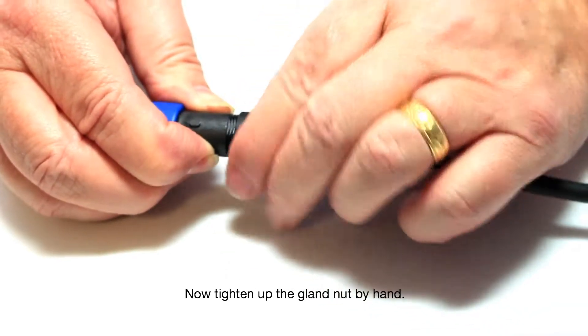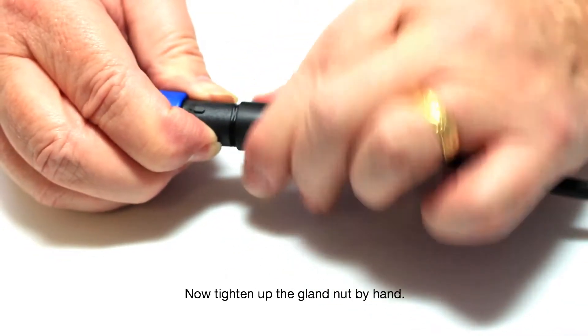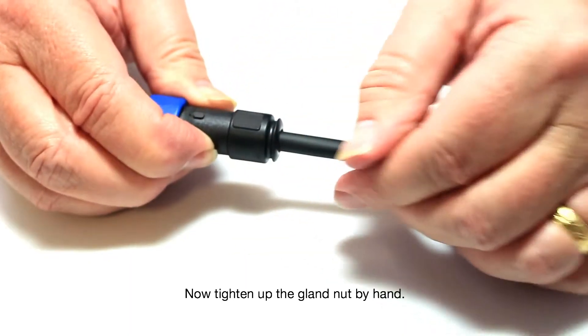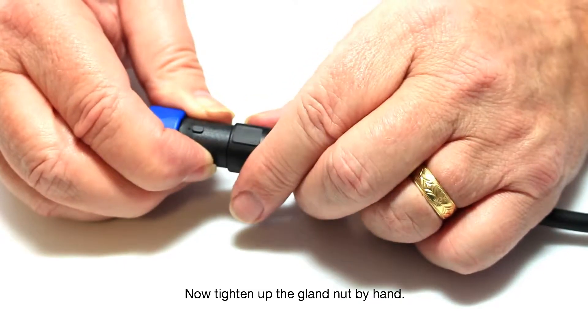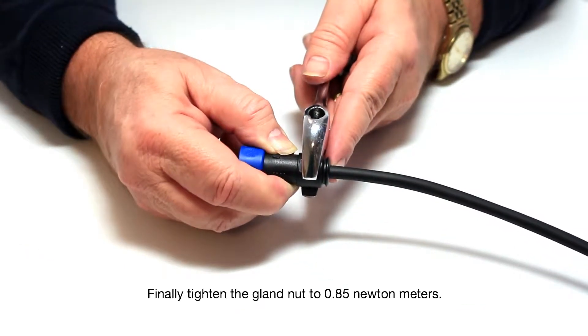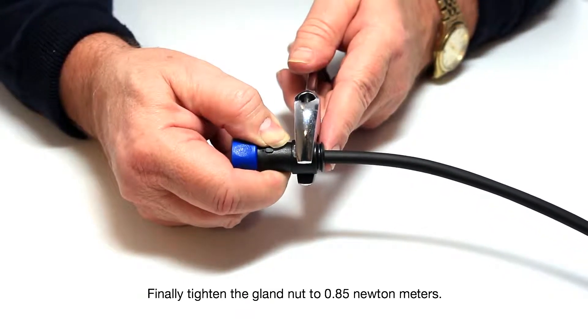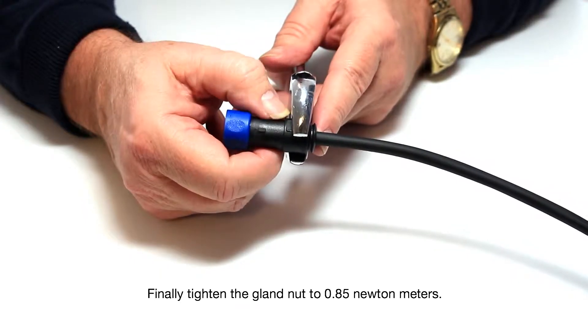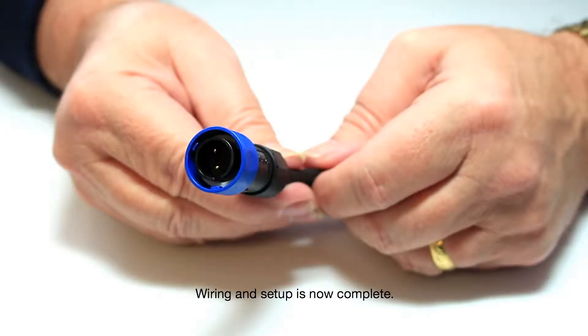Now tighten up the gland nuts by hand. Finally, tighten the gland nuts to 0.85 Newton meters. The wiring setup is now complete.